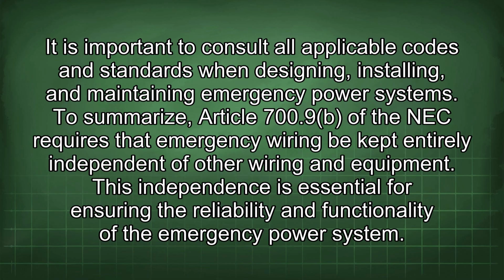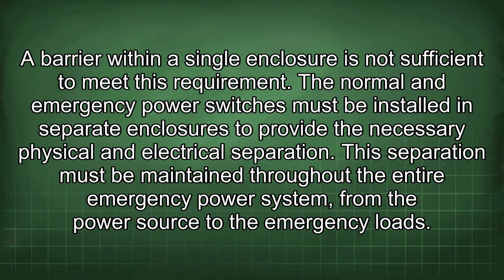To summarize, Article 700.9 of the NEC requires that emergency wiring be kept entirely independent of other wiring and equipment. This independence is essential for ensuring the reliability and functionality of the emergency power system. A barrier within a single enclosure is not sufficient to meet this requirement. The normal and emergency power switches must be installed in separate enclosures to provide the necessary physical and electrical separation. This separation must be maintained throughout the entire emergency power system, from the power source to the emergency loads.